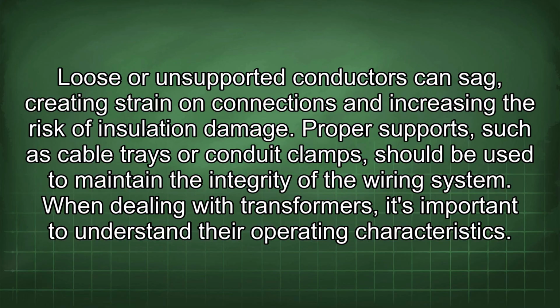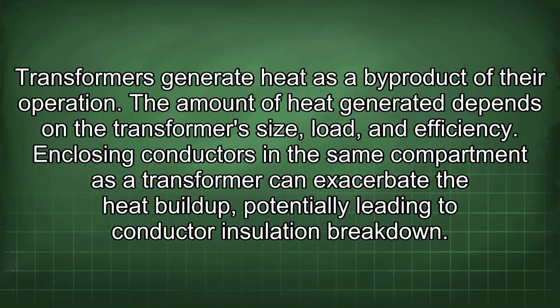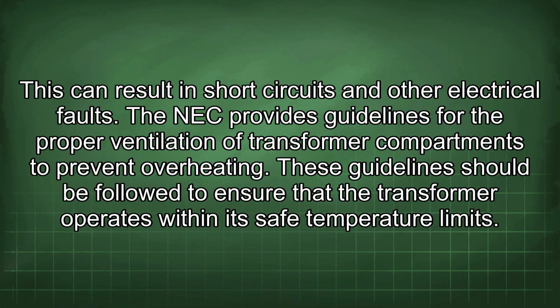When dealing with transformers, it's important to understand their operating characteristics. Transformers generate heat as a byproduct of their operation. The amount of heat generated depends on the transformer's size, load, and efficiency. Enclosing conductors in the same compartment as a transformer can exacerbate the heat buildup, potentially leading to conductor insulation breakdown. This can result in short circuits and other electrical faults. The NEC provides guidelines for the proper ventilation of transformer compartments to prevent overheating. These guidelines should be followed to ensure that the transformer operates within its safe temperature limits.